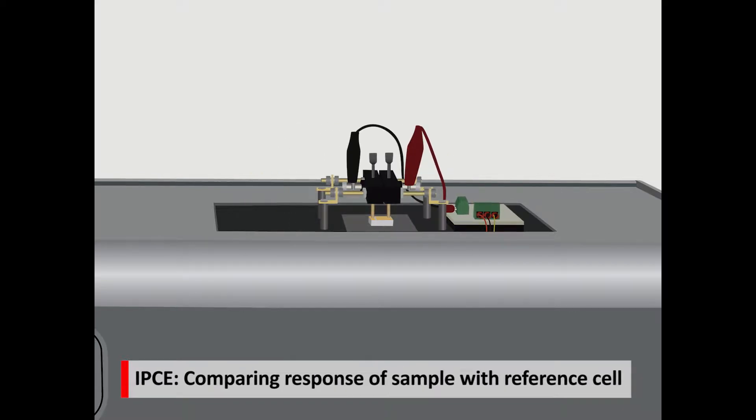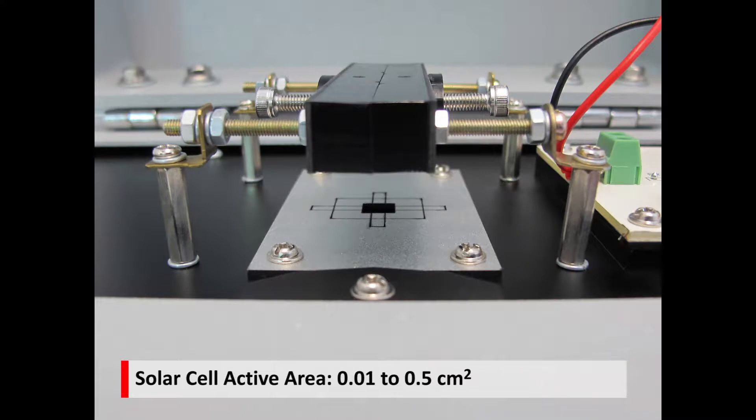Measuring IPCE is made by independent measurement of both sample and reference cell. Solar cell samples of maximum 0.5 cm² can be tested with this system.